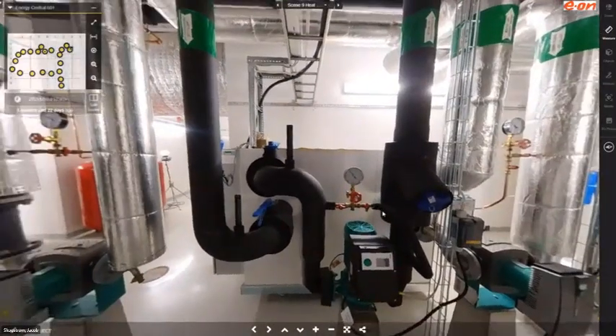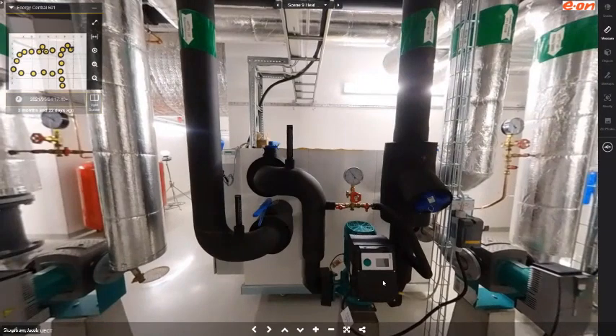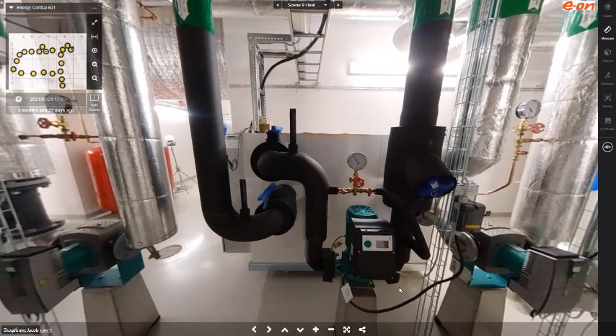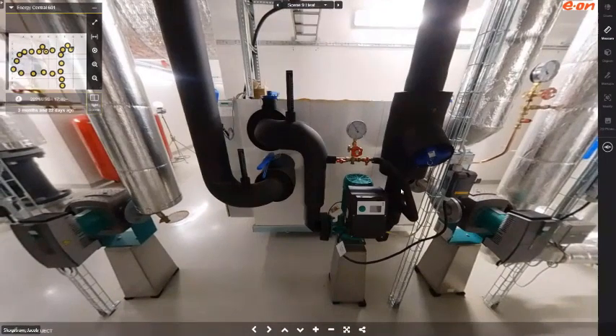If we look at the heat pump, we can also discuss one of the innovations with Ectogrid. Normally in a district heating grid, there's always a big circulation pump creating rotation of the fluid in the system, going forward and then back on the return pipe. In Ectogrid, we have smaller pumps instead in each building, removing the large pump in the outside grid.